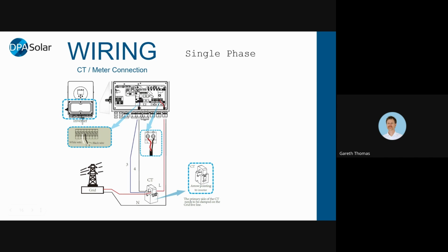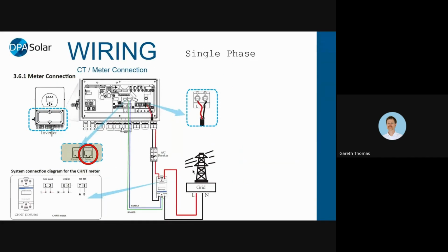Do you know how long the cable is, David? I think it's a 3-meter cable. Yeah, okay, pretty good. Instead of using the supplied CT, you can use a meter. That's going to go back to an RJ45 plug on the main board here called meter, and there's a little wiring diagram for that here. So if you want to have that in the main switchboard and have the inverter somewhere else, for instance, then you might use the meter.